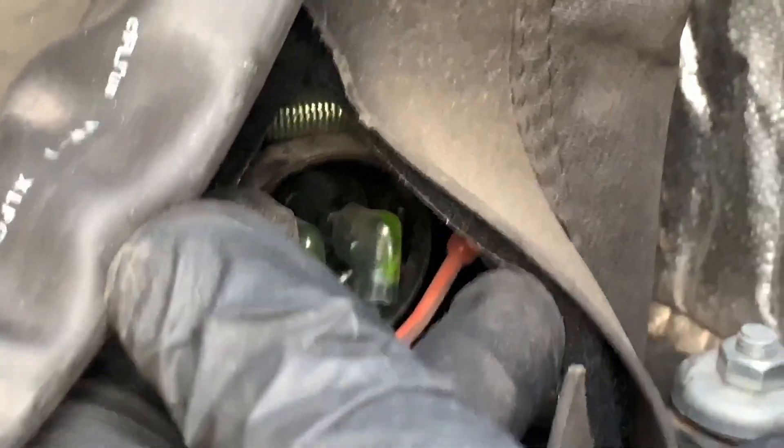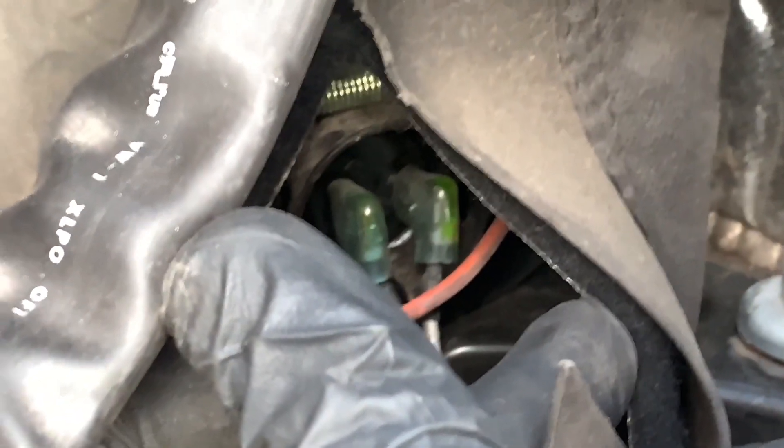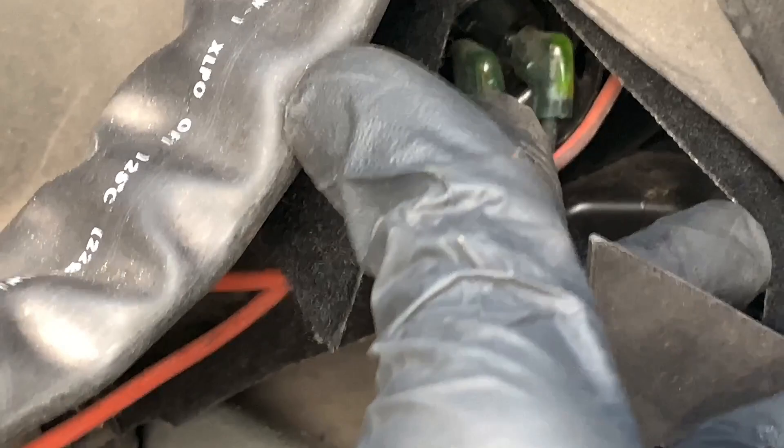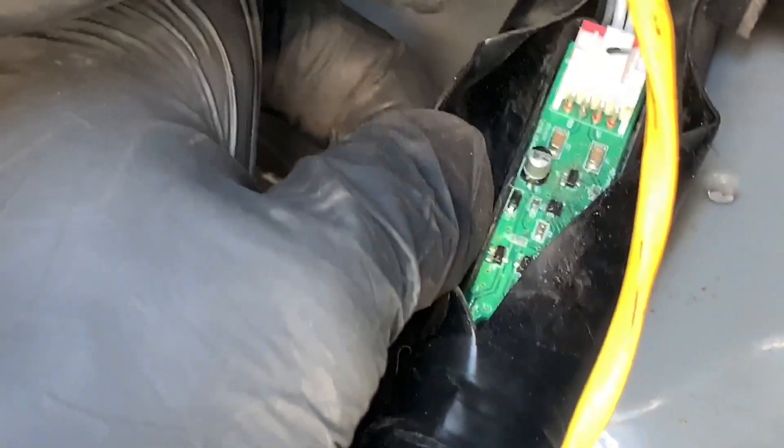As you can see, that's it - just those two wires going into the terminal block on the bottom of the compressor that senses the oil level. I don't know exactly how it does it, but that's how it does it. Those two wires go back into a module right here. So this is the module that converts those two wires into another plug on the other end.